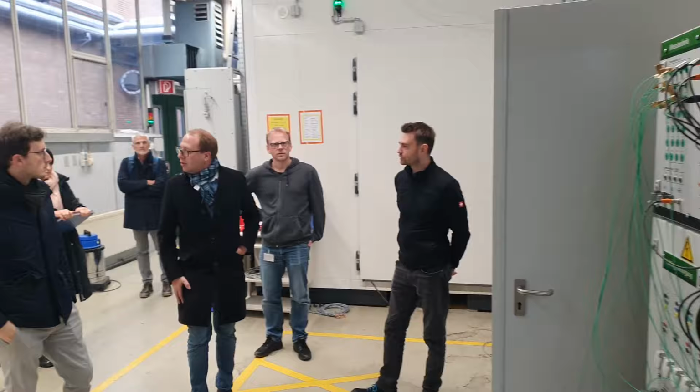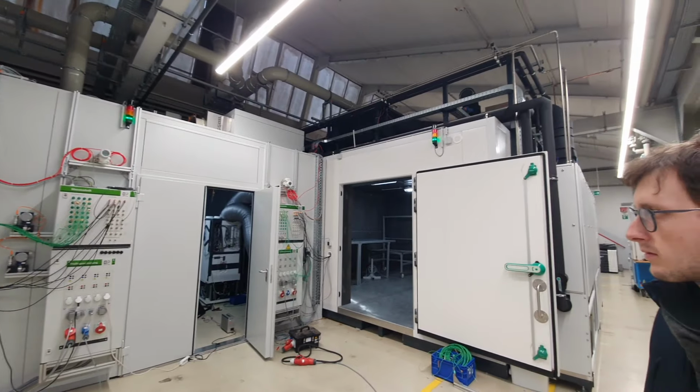At the start of the tour, we were taken to the rooms where heat pumps are tested, but unfortunately I couldn't record much because they were already testing the new R290 heat pump, which will hit the European market next year. There are tons of tests used to stress the machines. Heat pumps are tested from -25 to +45 with an output temperature of about 75 degrees Celsius to check the engineering efficiency of the compressor and evaporator and all the components, which we will soon see how they're made.